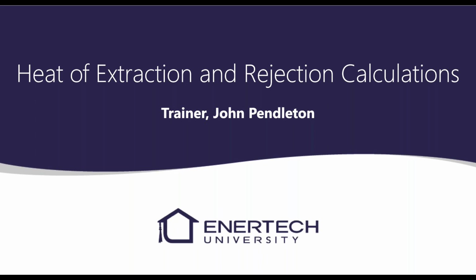So on to the heat of extraction and heat of rejection. Basically, the calculation is no different when you're going from one mode to the other. We're still doing the same calculations. We're just either extracting from the loop field or we're rejecting to the loop field, and that's heat. No refrigerant gauges are needed. It verifies equipment performance by measuring the amount of heat that's either being rejected or extracted from the loop field.